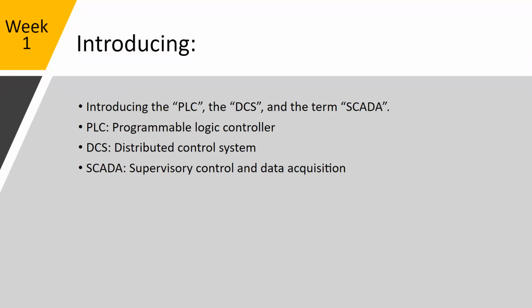So the PLCs are typically the brains of any individual system. Sometimes you'll have multiple PLCs, like in manufacturing facilities or treatment plants for water, oil and gas. You could have many PLCs communicating with one another for all the different subsystems. The DCS systems are typically a little more robust, if not slower. They're meant for very large facilities, utility level, power generation, oil and gas stuff, facilities and pipelines.